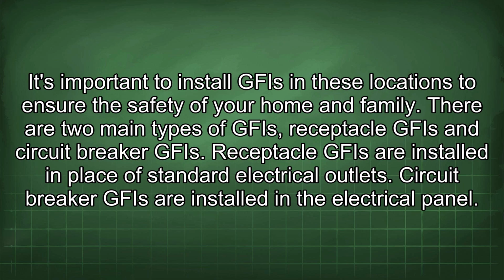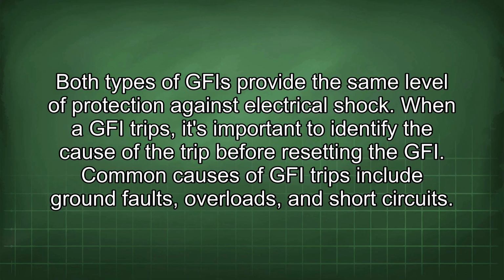There are two main types of GFI: receptacle GFI and circuit breaker GFI. Receptacle GFI are installed in place of standard electrical outlets. Circuit breaker GFI are installed in the electrical panel. Both types of GFI provide the same level of protection against electrical shock. When a GFI trips, it's important to identify the cause of the trip before resetting the GFI. Common causes of GFI trips include ground faults, overloads, and short circuits.